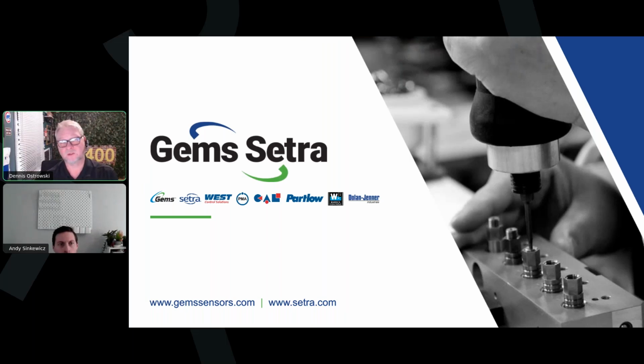And that's why, like I said, there are 10 different calibration settings: M factor, K factor, zero offset, 2-point offset. There are tons of things that you can do in there to dial it into your specific requirements. But again, it's going to be a try it and see. You're going to have to get one, try it out, see if it works in that application, see if it can be dialed in using all of the calibration settings that are offered.